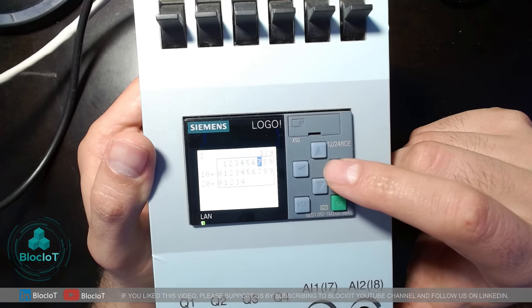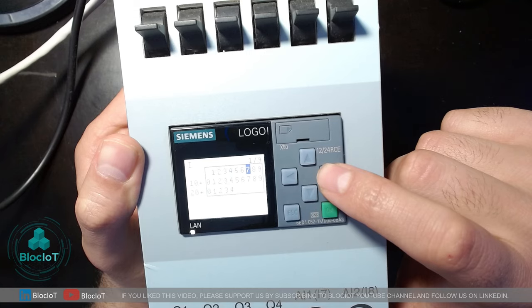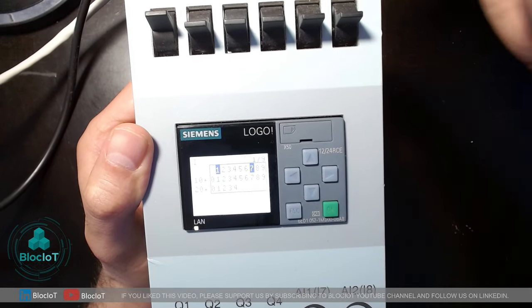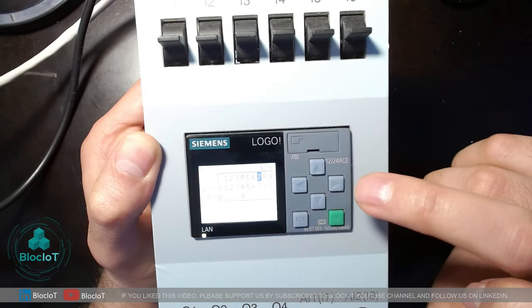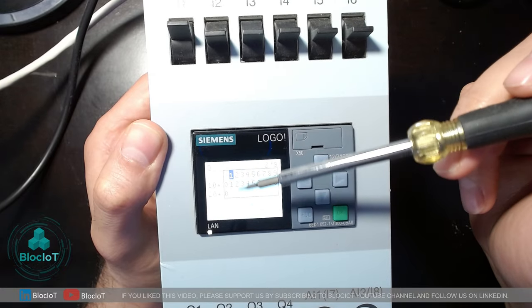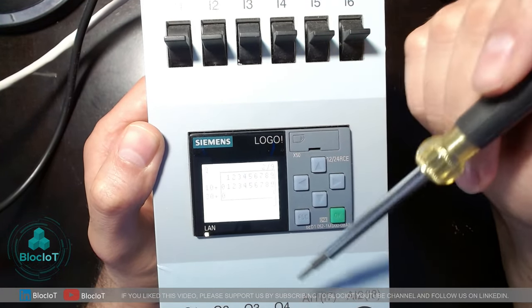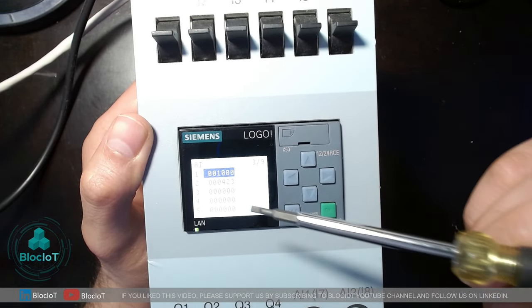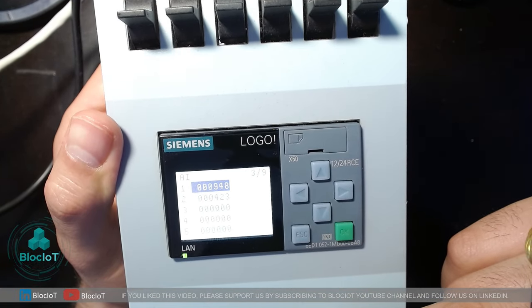Apart from the settings menu, there are nine different screens on the Logo accessible by pressing the right arrow key. The first screen shows the status of your inputs — if I switch input number one, the display shows it highlighted or in a true/one state. Scrolling right again shows the status of outputs (Q), so when I trigger input number one it triggers output Q1, which I can monitor right on the Logo display. The third screen shows the value of analog inputs, which is very handy for troubleshooting.